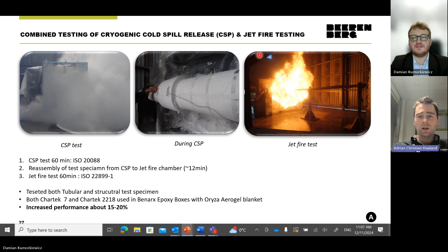Here you see an immersion test where we actually filled the entire panel system with a couple hundred liters of liquid nitrogen, and you can almost hear the top coat making small cracking, sparkling sounds when you pour the liquid nitrogen, due to the thermal expansion and all the joints moving a little bit and contracting. We have seen formulas and products which break clean off the steel because of this. So not every combination of material will withstand it. If the difference in thermal contraction between the substrate and the applied PFP is too big, it will just crack itself off due to the thermal movement of the two materials.